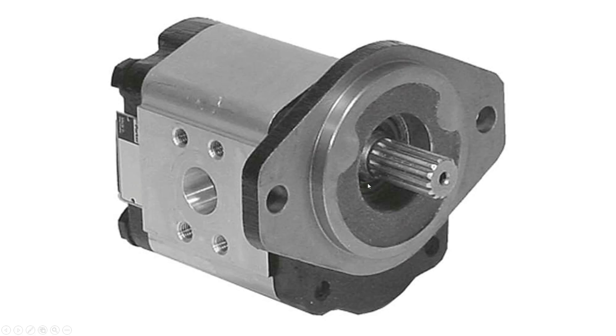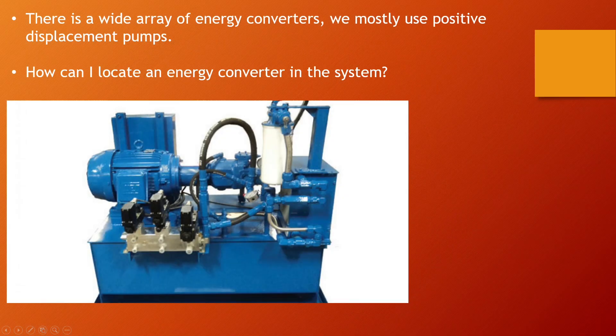This is a classic picture of a gear pump — an energy converter that converts mechanical energy into fluid flow energy. This is where we couple the electric motor to the shaft of the gear pump, and this is where we connect our inlet; on the other side are the outlet ports for fluid flow. We mostly use positive displacement pumps when talking about energy converters, and they work by changing volume — by changing the work volume they convert the energy.